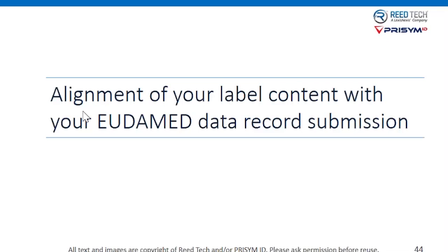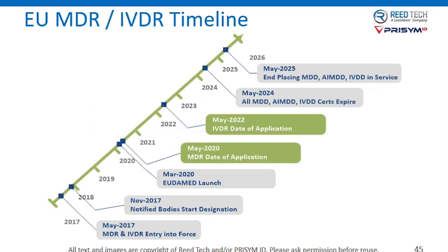But one of the things that comes up in all these discussions is what is the timing for the various activities and the milestones. And as Mark had mentioned, the labeling activity has significant effort connected with it. In parallel, I would suggest that you also want to start to look at the data sets and that particular collection of data, verifying the contents and so on, that need to be part of your product registration and also of the UDI reporting to the EUDAMED, which is the European database.